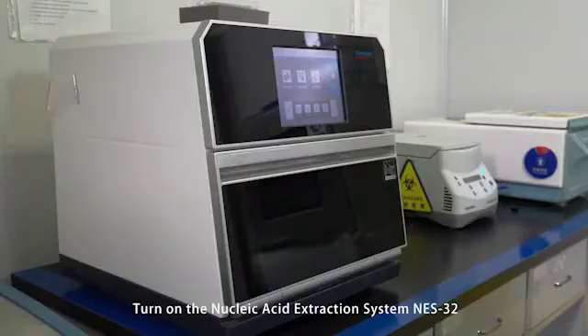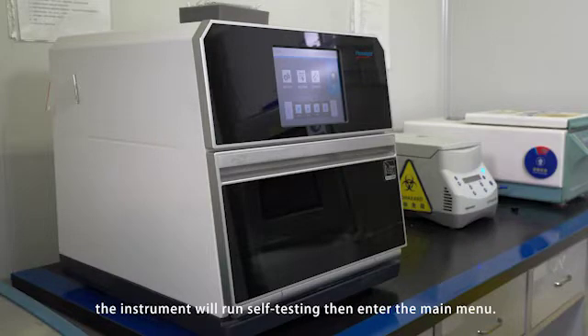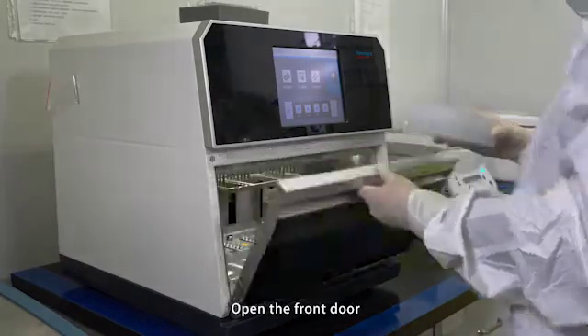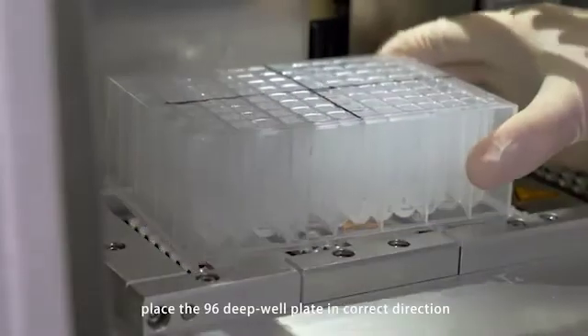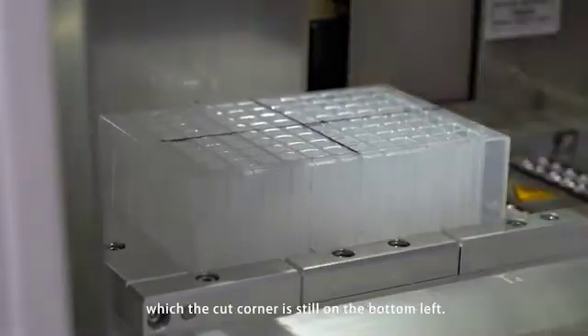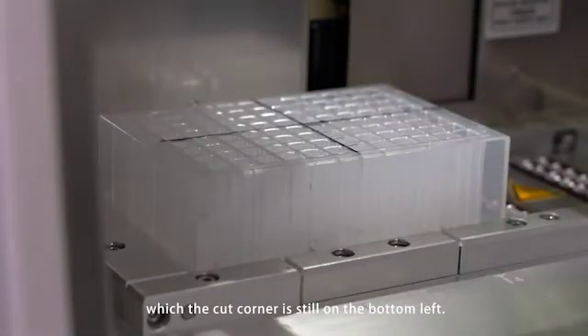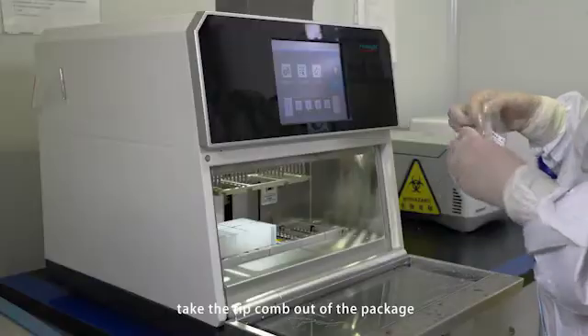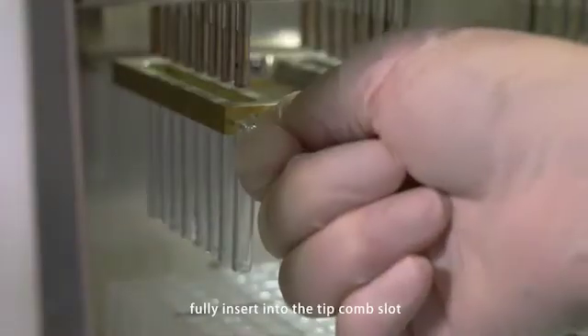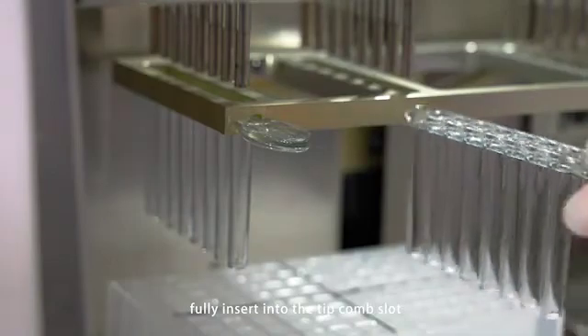Turn on the Nucleic Acid Extraction System NES32. The instrument will run self-testing, then enter the main menu. Open the front door. Place the 96 deep well plate in correct direction, which the cut corner is still on the bottom left. Take the tip comb out of the package. Fully insert into the tip comb slot.